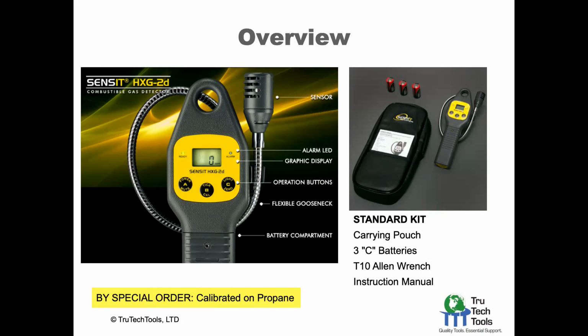So when you get the unit, it includes a carrying pouch, the batteries, a wrench to actually open up the battery compartment, and an instruction manual. A wrench to open the battery compartment. You may say, what the heck, what's that all about? This instrument is actually designed for gas utilities and fire departments, and they cannot afford to have batteries falling out on the job. It's not that it's a weak design, but it's suspenders and belt, it's going to stay in place. That battery cover is going to stay in place.